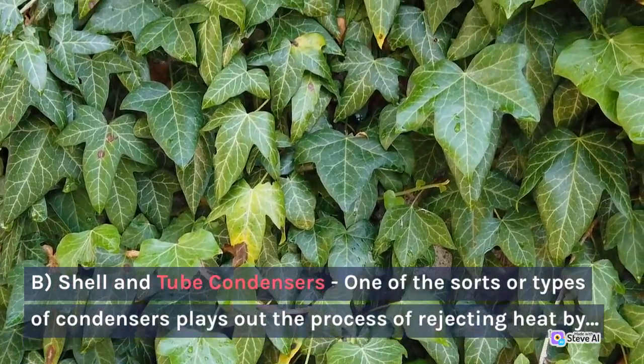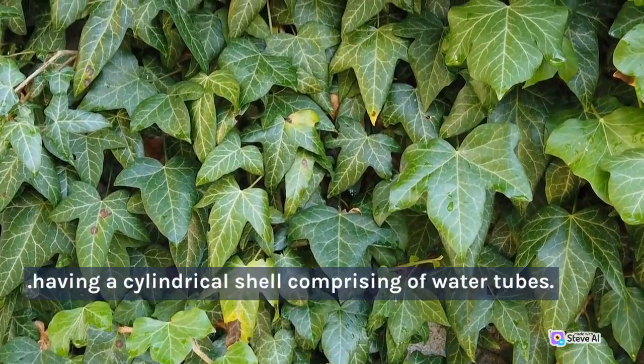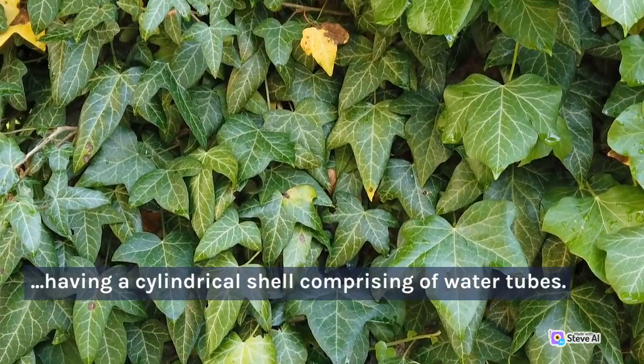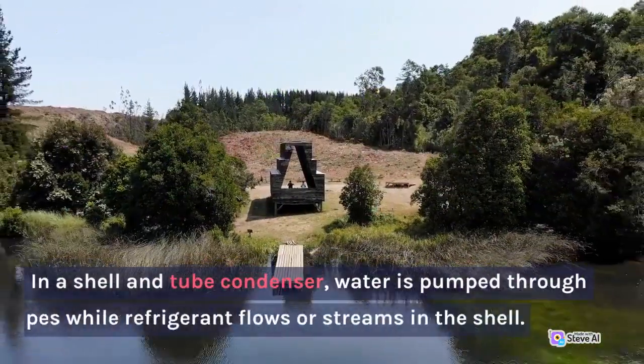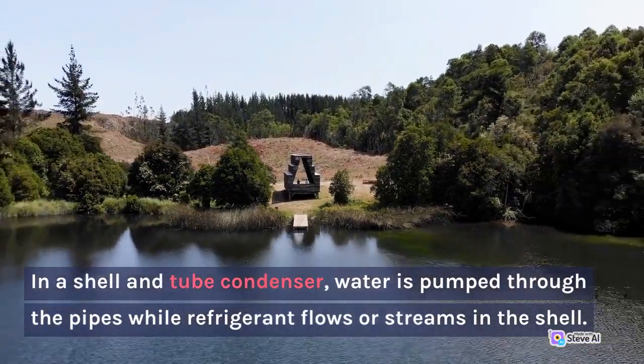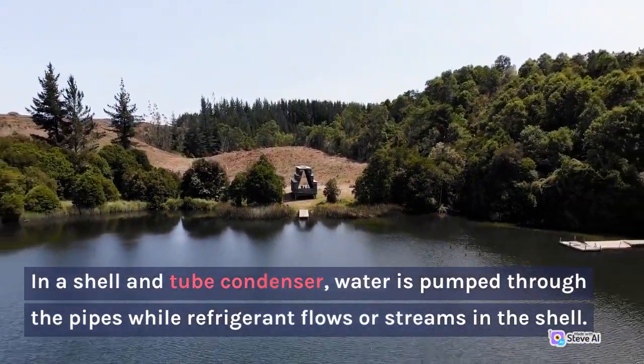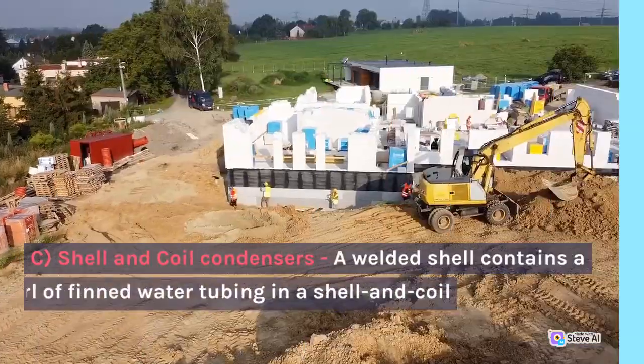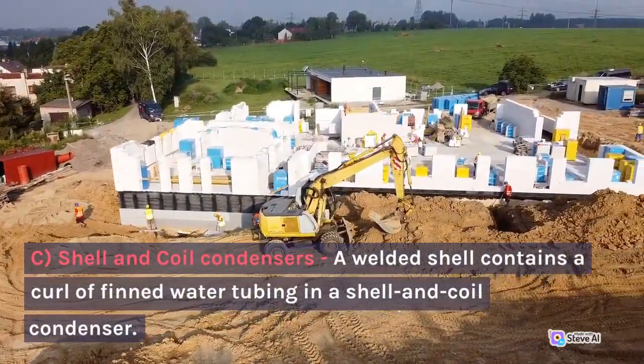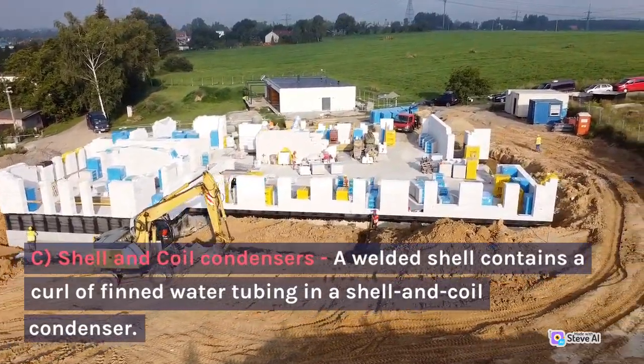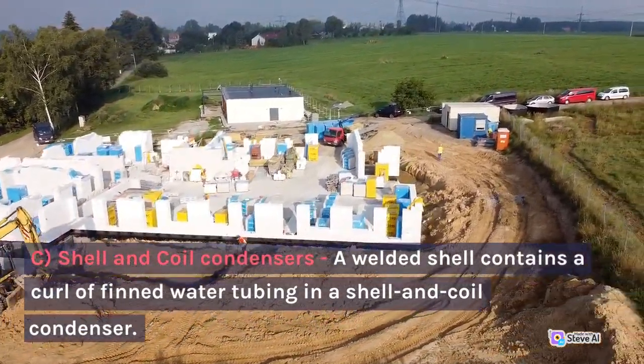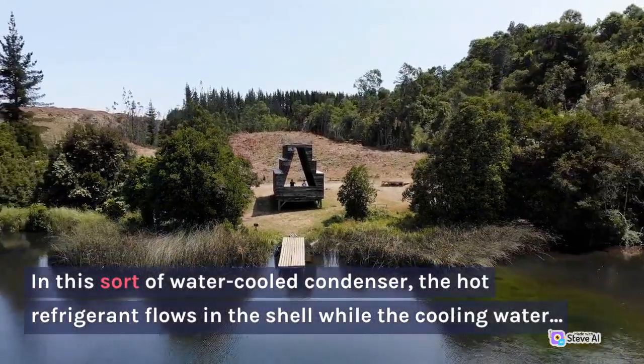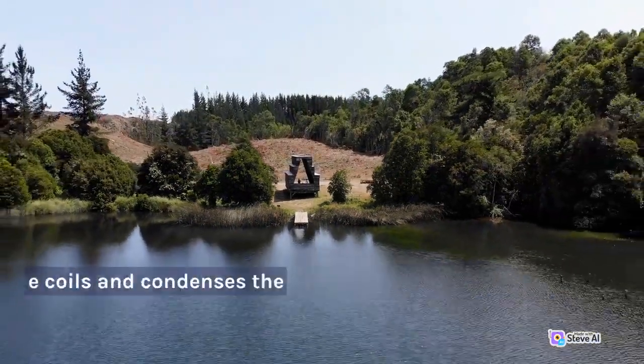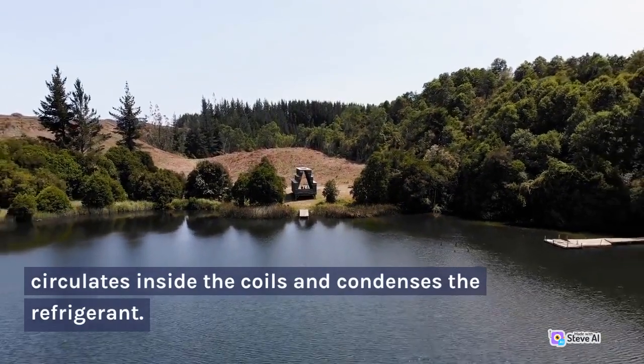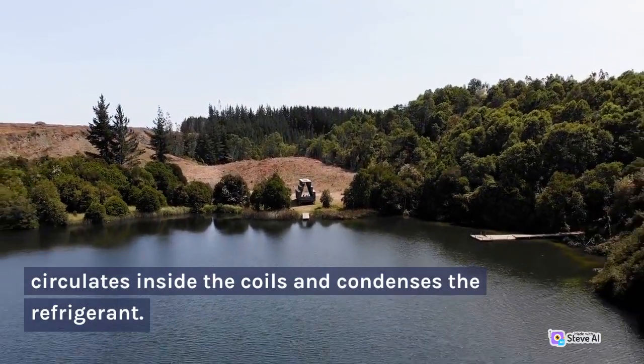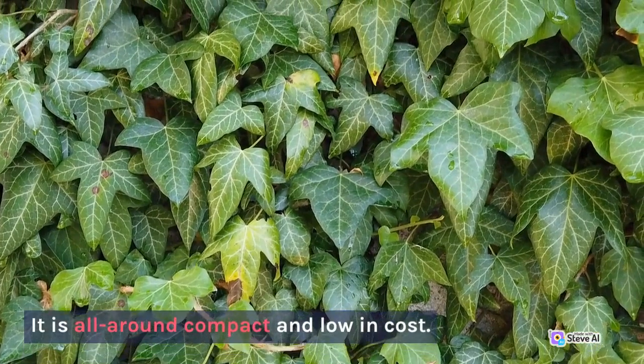One of the types of condensers performs the process of rejecting heat by having a cylindrical shell comprising water tubes. In a shell and tube condenser, water is pumped through the pipes while refrigerant flows in the shell. C. Shell and coil condensers. A welded shell contains a coil of finned water tubing in a shell and coil condenser. In this type of water-cooled condenser, the hot refrigerant flows in the shell while the cooling water circulates inside the coils and condenses the refrigerant. It is quite compact and low in cost.